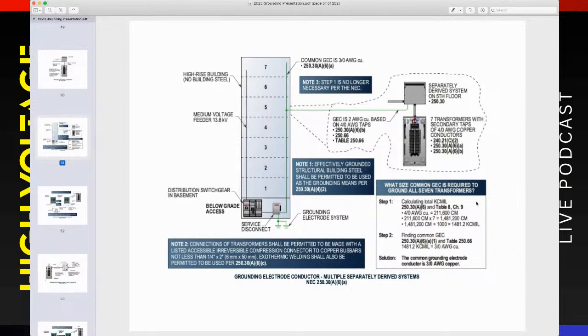We ask you: what size common grounding electrode conductor is required to ground the 7 transformers for each? We show you how to get the circular mil, multiply it by the 7, giving you your circular mil and KC mil, then go look at Table 250.66, and it tells you it needs to be a 3-aught conductor—and it never has to be larger than a 3-aught. We're showing you how to go get that from the table.